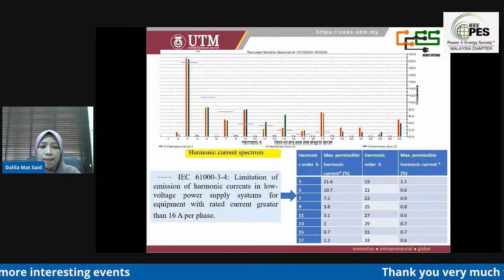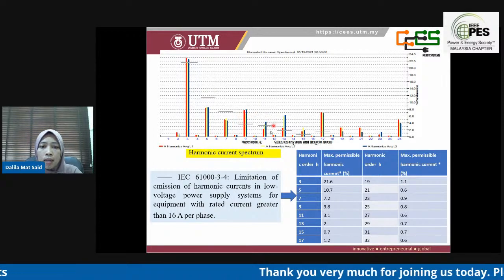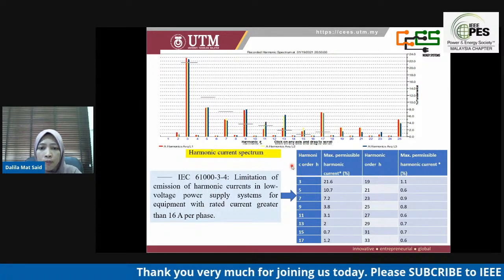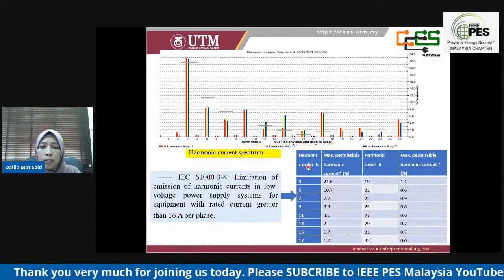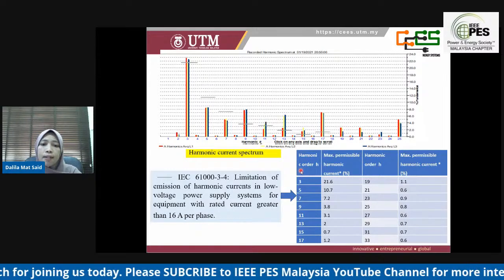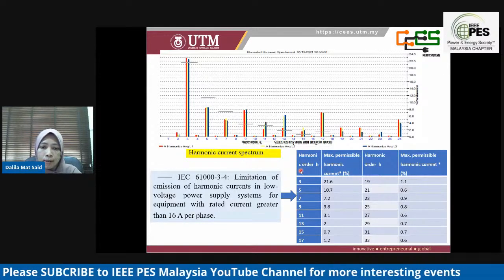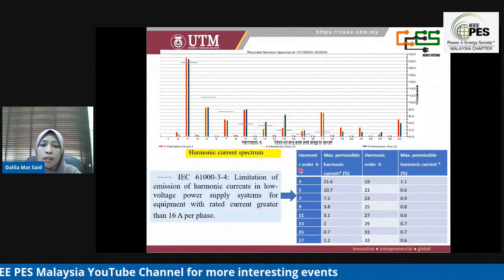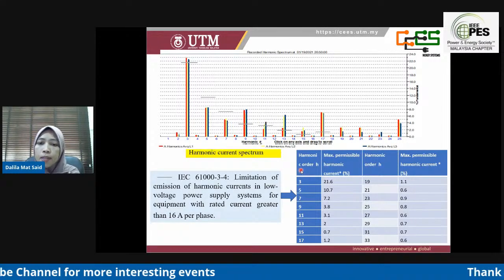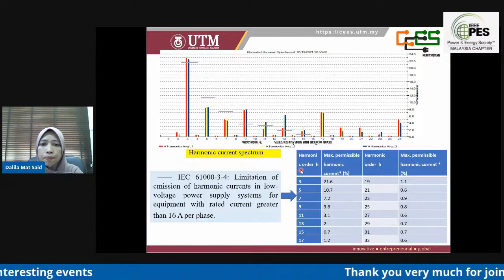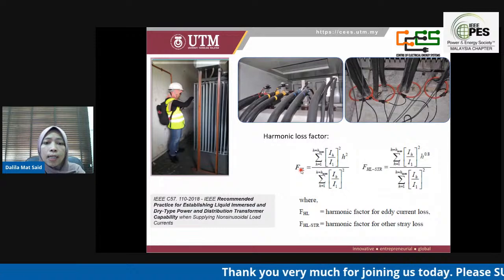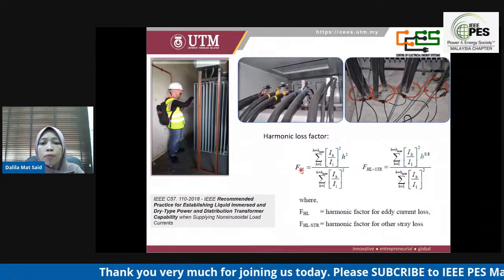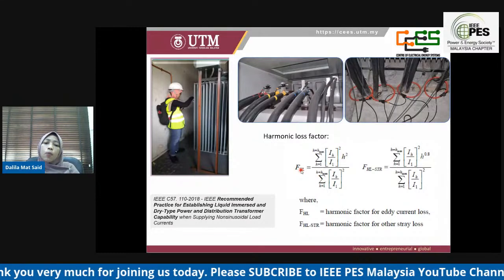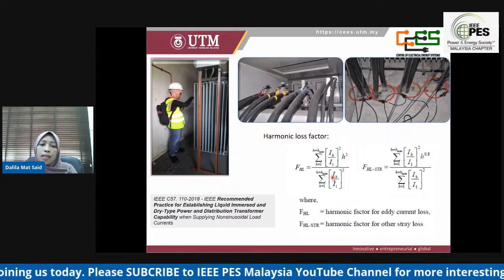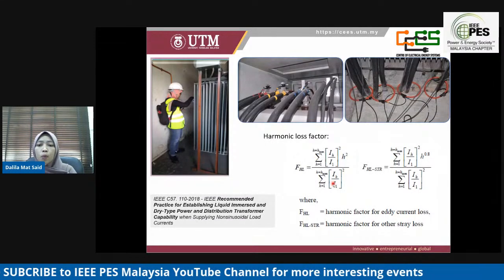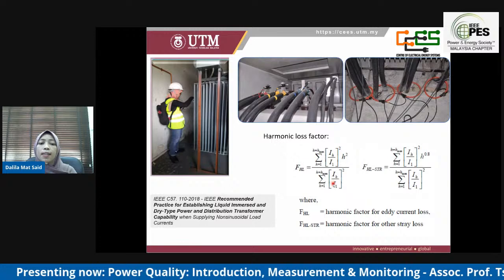We can see the 3rd, 9th, 11th, and also the 17th order harmonics have exceeded the limit. This excess will increase heating and also increase the losses, especially in the power system. From the data also, in order to study the impact of harmonics on the transformer, we consider what we call the harmonic loss factor. This harmonic loss factor is identified by considering the contribution of all individual harmonic data.